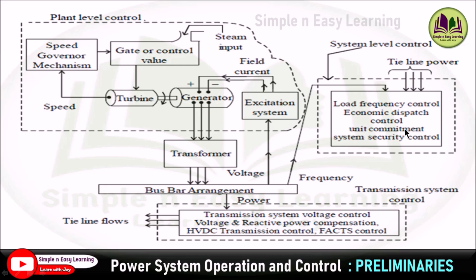The next one is unit commitment. Economic dispatch gives the optimum schedule for one particular load on the system, but the unit commitment problem is used to find the shutdown and commissioning rules so that the total cost of generation for a given period of time is minimum. The load demand on the power system varies throughout the day and reaches different peak values from one day to another. To meet the varying load demand, different combinations of generators are operated. Power system engineers need to know the sequence of generating units to be operated, considering minimum cost during increase and decrease in load demand.